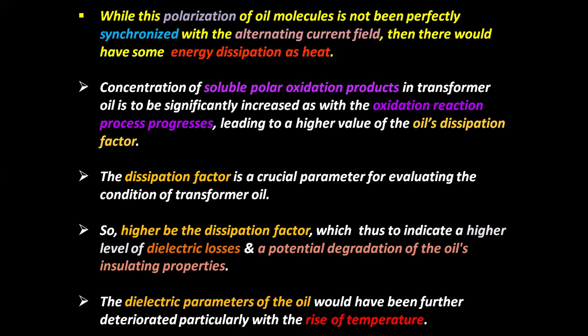The dissipation factor is a crucial parameter for evaluating the condition of transformer oil. So, the higher the dissipation factor, the higher the level of dielectric losses and the potential degradation of the oil's insulating properties. Again, I repeat: the higher the dissipation factor, the higher the level of dielectric losses and the potential degradation of the oil's insulating properties. The dielectric parameters of the oil are further deteriorated, particularly with the rise of temperature.